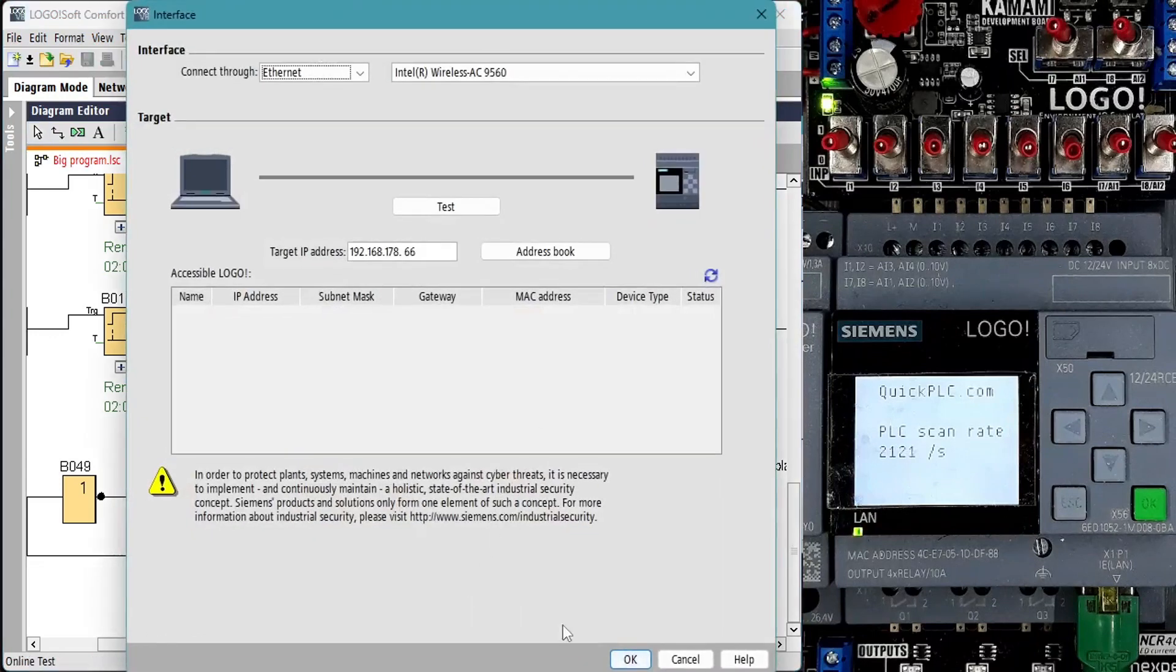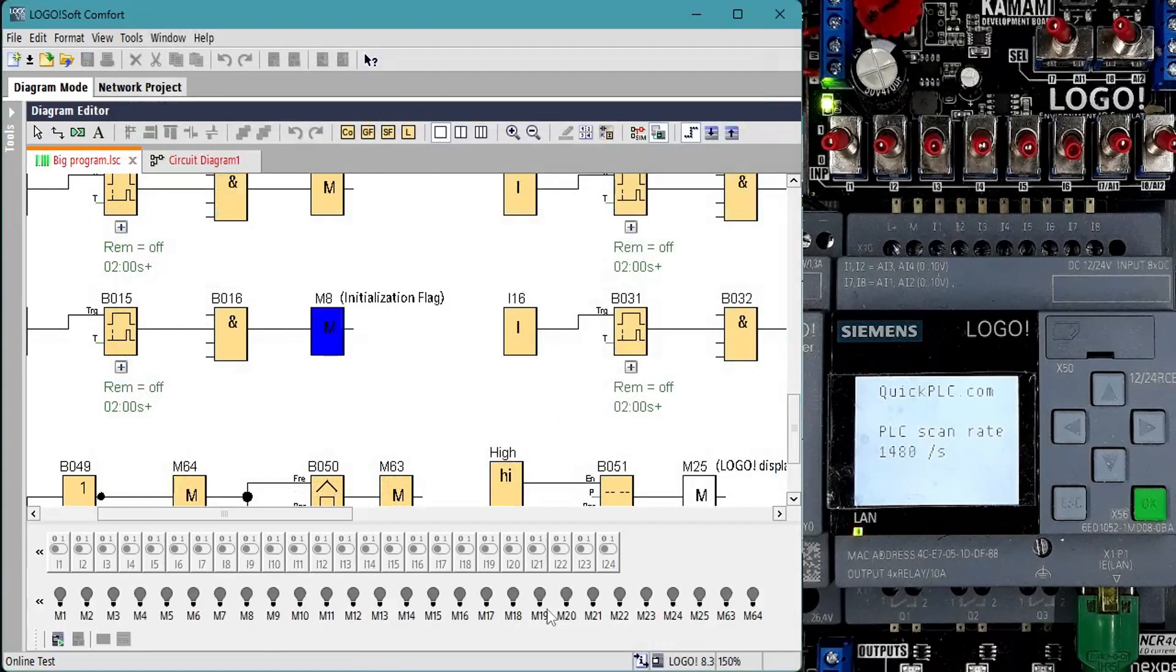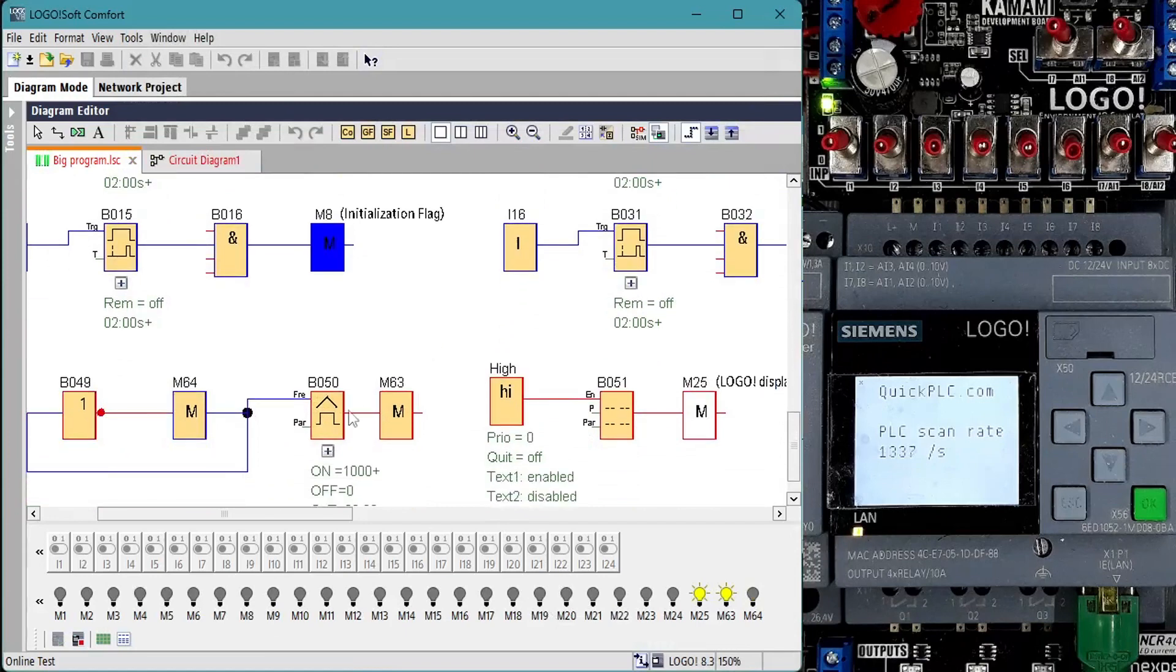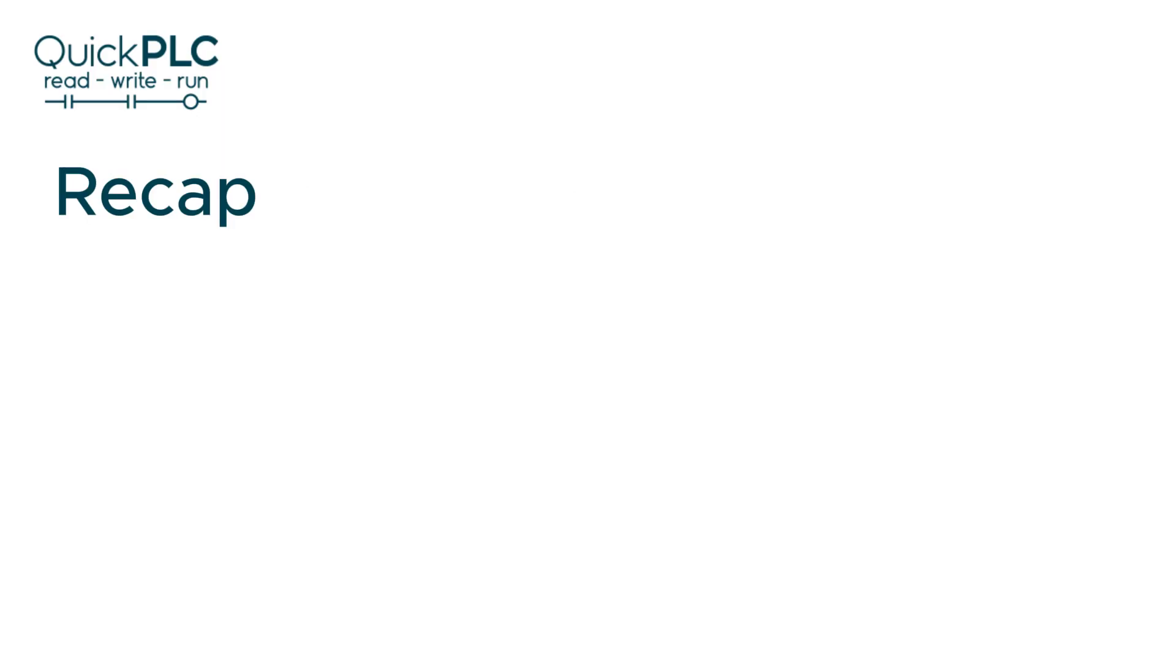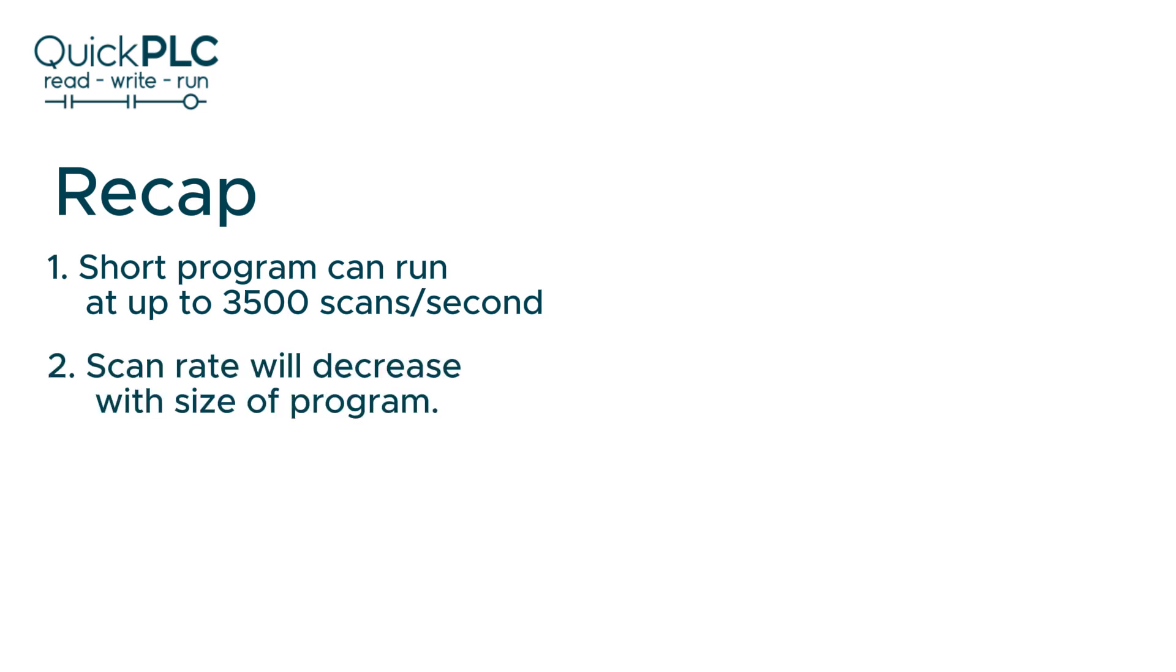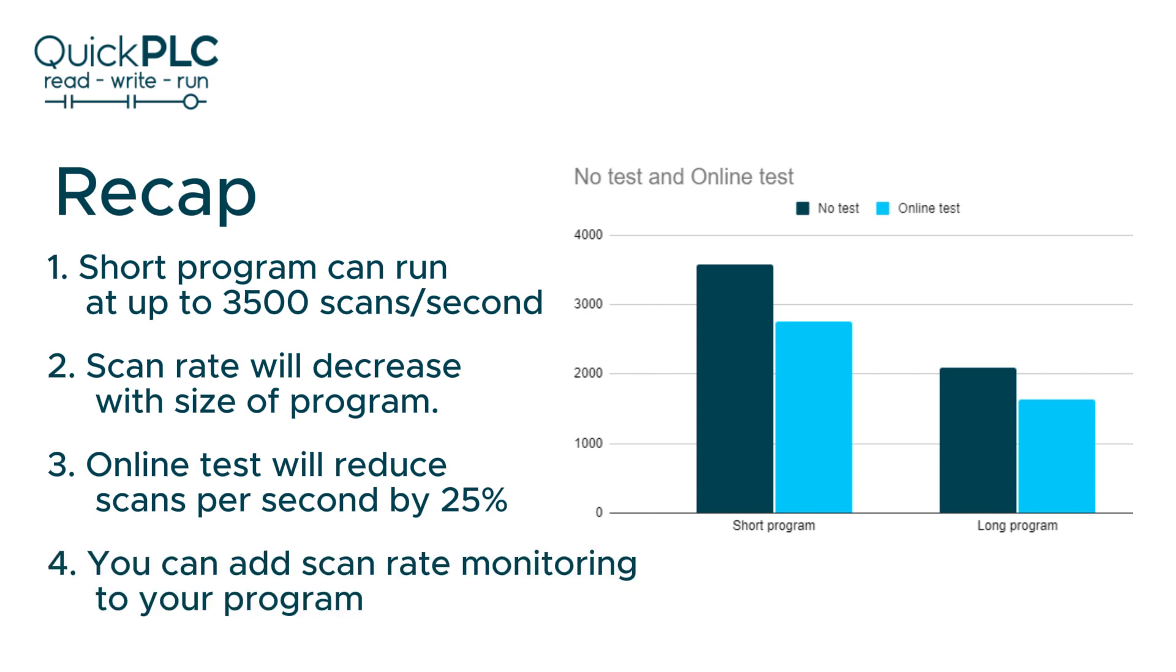Running online test drops the scan rate by almost 25% as before. Based on these simple tests it looks as though the overhead of reading the inputs, basic housekeeping and writing the outputs is going to take at least 0.3 milliseconds. Scan rate will be further decreased in proportion to the size of the program. Scan rate will drop by 25% when running online test. And we learned that it's easy to add scan rate monitoring to your program.